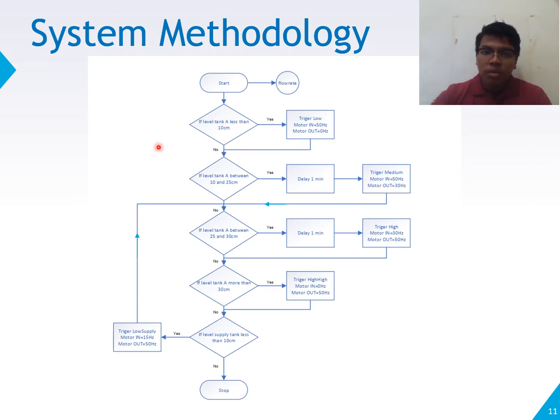Then, the water level will slowly increase, and when it reaches the set point level between 10 and 25 cm, the PLC ladder diagram programming will trigger a medium signal, and the outgoing motor speed is adjusted to 30 Hz, while the incoming motor speed is 50 Hz. Next, when the level reaches a value between 25 and 30 cm, the program will trigger a high signal, and the incoming motor speed is adjusted to 30 Hz, while the outgoing motor speed is set to 50 Hz.